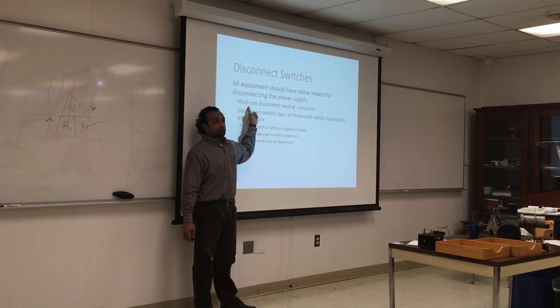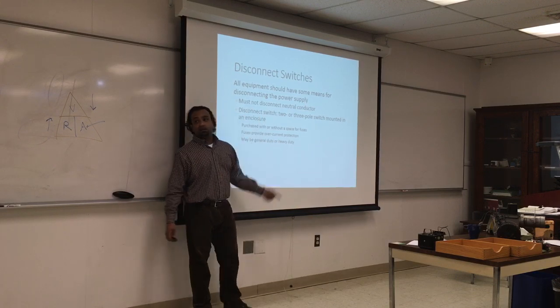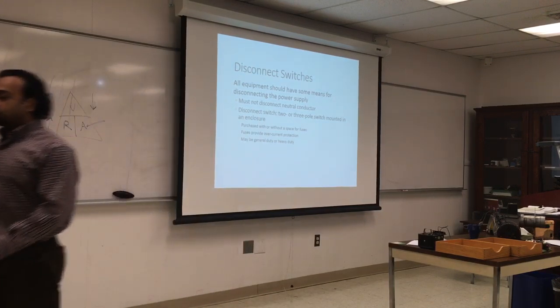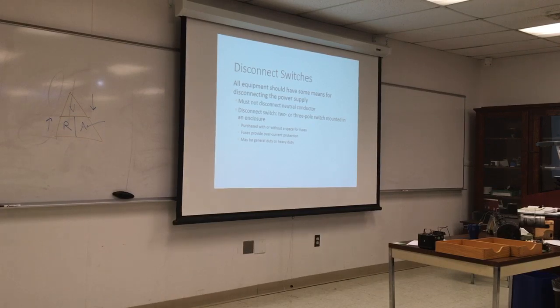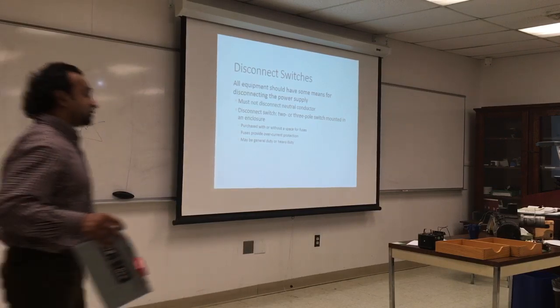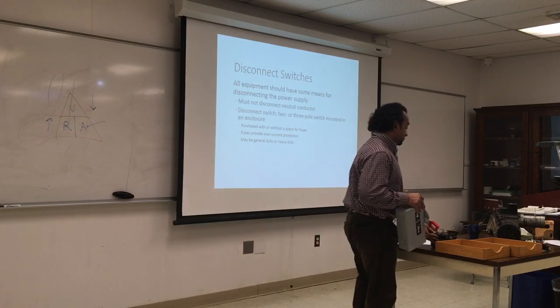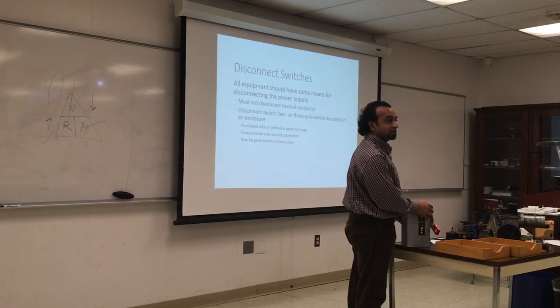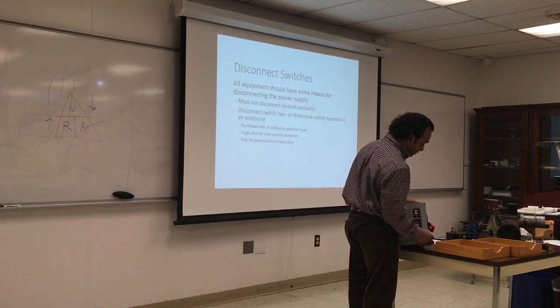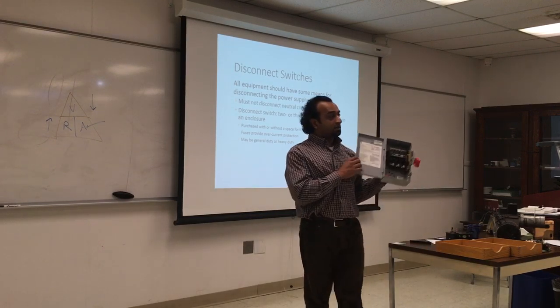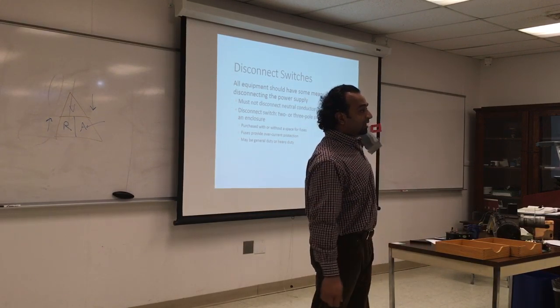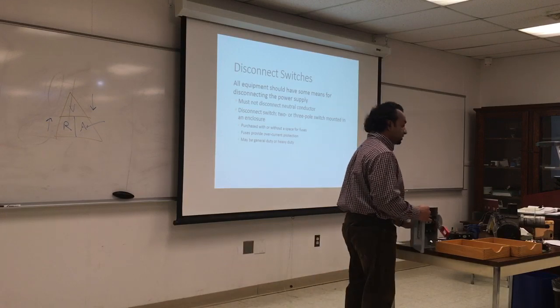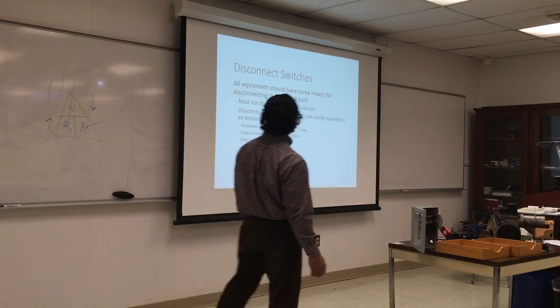That's a very important piece of information. No, it's not. You do not put a disconnect switch on the neutral. Always the hot. Same reason why we don't put fuses on the neutral, because we are trying to protect the circuit, and the neutral is the line coming back, so it doesn't make sense to put things on the neutral. So if you look at a disconnect switch, the fuse lines are the hot lines, whether they're one phase or three phase.